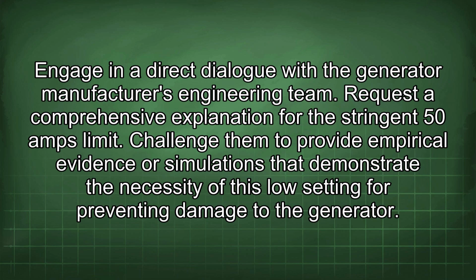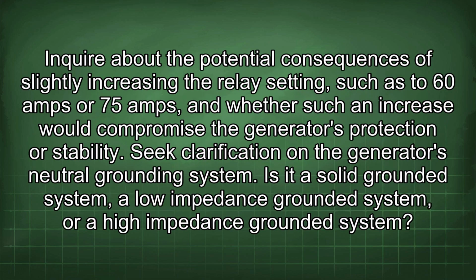Engage in a direct dialogue with the generator manufacturer's engineering team. Request a comprehensive explanation for the stringent 50 amps limit. Challenge them to provide empirical evidence or simulations that demonstrate the necessity of this low setting for preventing damage to the generator. Inquire about the potential consequences of slightly increasing the relay setting, such as to 60 amps or 75 amps, and whether such an increase would compromise the generator's protection or stability.